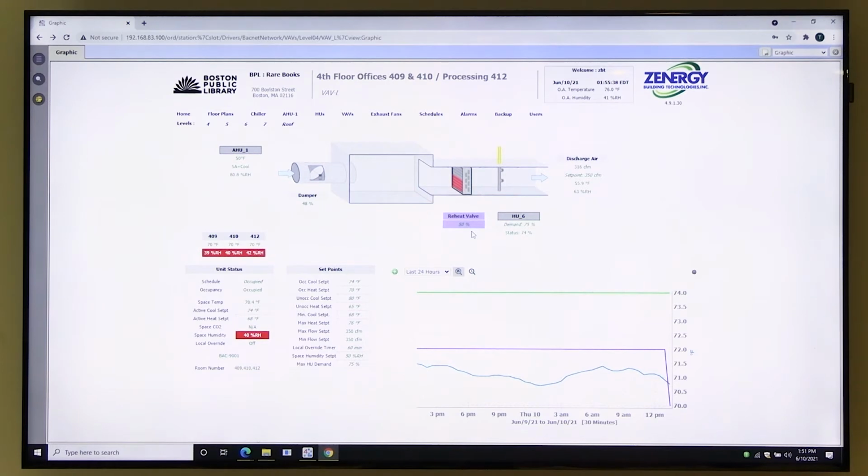So if I were to go to this VAV box and I saw that this reheat valve was at 50%, or say it was at 0%, but the background was purple, if I went up to that box and turned the power off on it and then turned it back on, the graphics here would still say that it's overridden because the server, like the BMS, still thinks it's an overridden point, but that controller actually lost that override. It got cleared out when the power cycle happened.